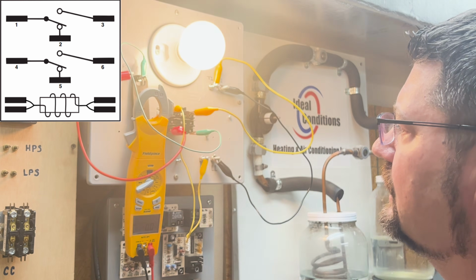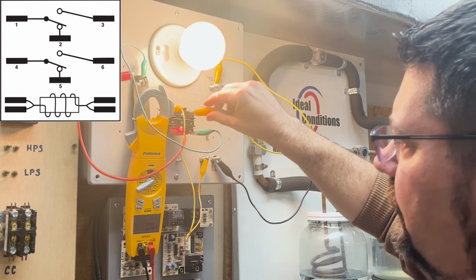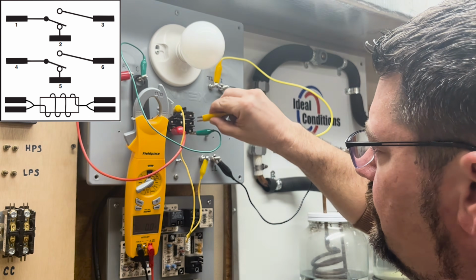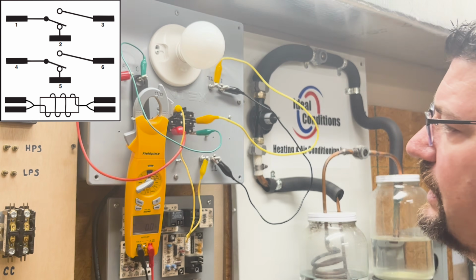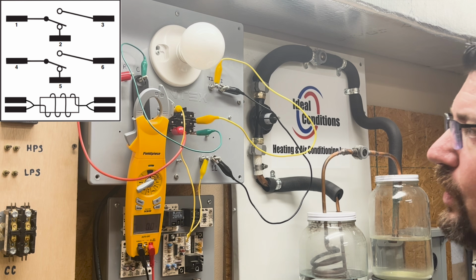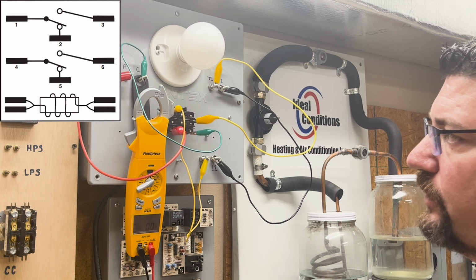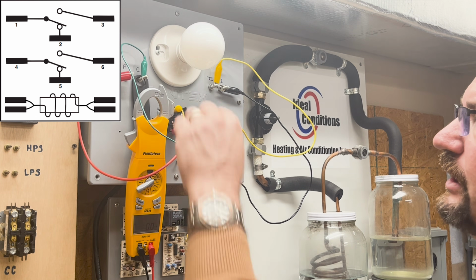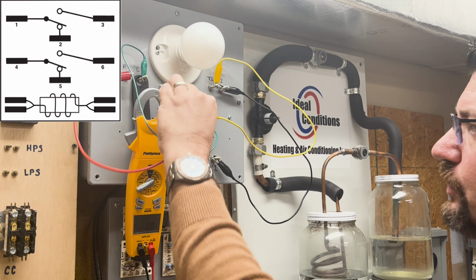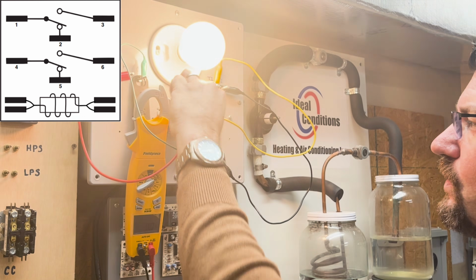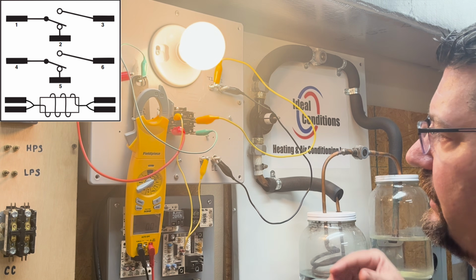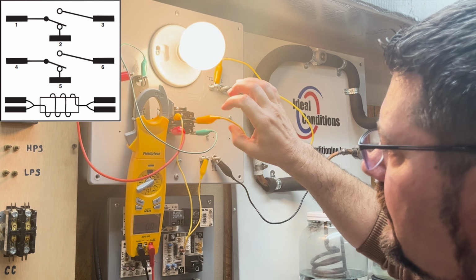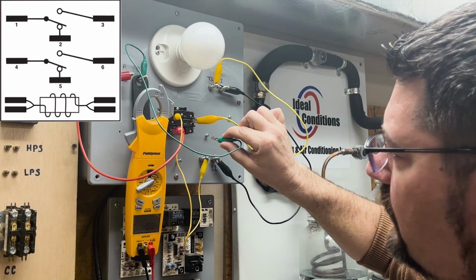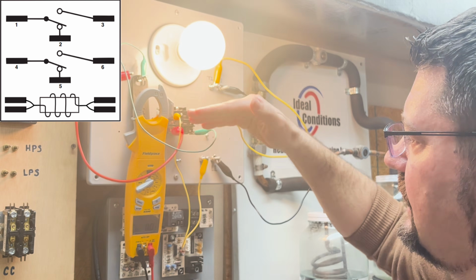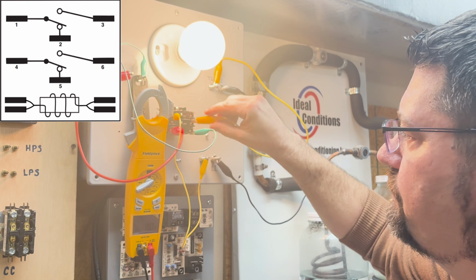So I'm going to go ahead and do the same thing. I'm going to run this down to terminal 6, which is on the second pole. That second pole has no power on terminal 4, which is the line voltage terminal. So I'm going to have to put line voltage on 4, and the load will come back on. And it's simple as that. I'll move the 24 volts off of it. And as you can see, that second pole is doing the same thing that that top pole is doing.